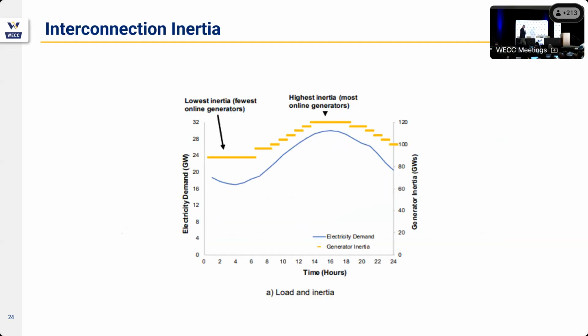So this is typically what inertia looks like when you compare it to demand. As your demand goes up, your inertia goes up. That basically means as you bring every machine on, additional peaking units throughout the day, your inertia will go up as your demand goes up. Your lowest generation historically has always been middle of the morning or early in the morning, right after midnight. In the West, it was always about 4 a.m. So this is what we always would expect inertia to look like.